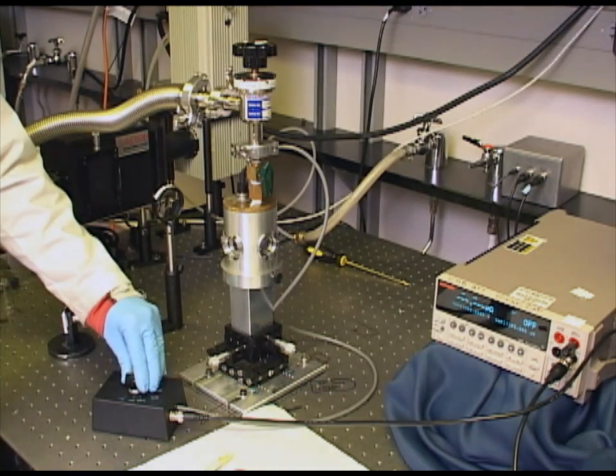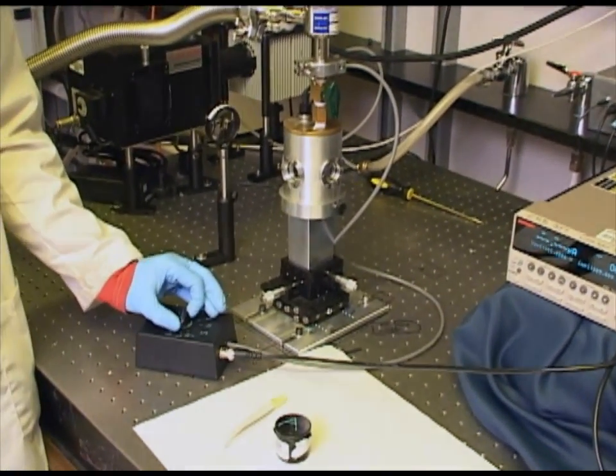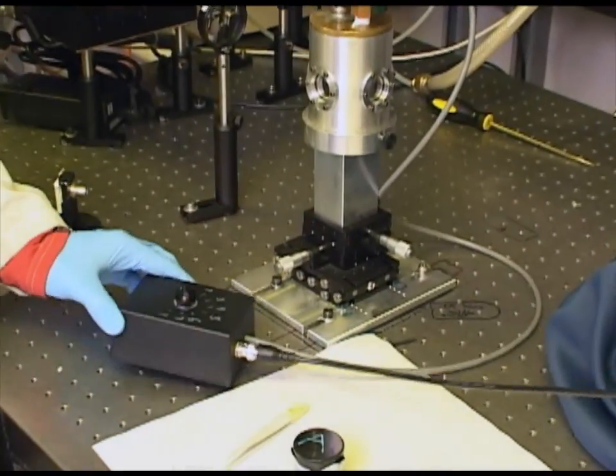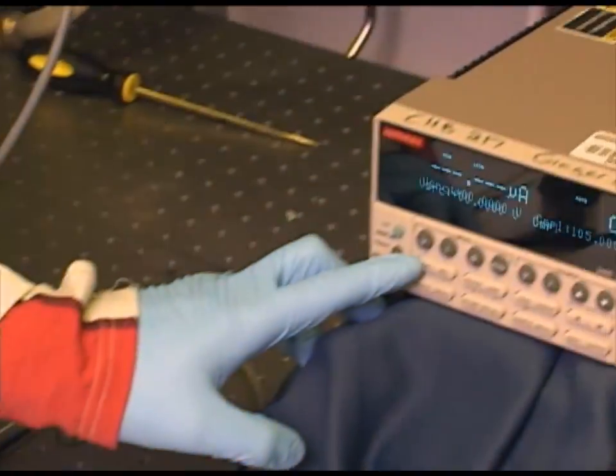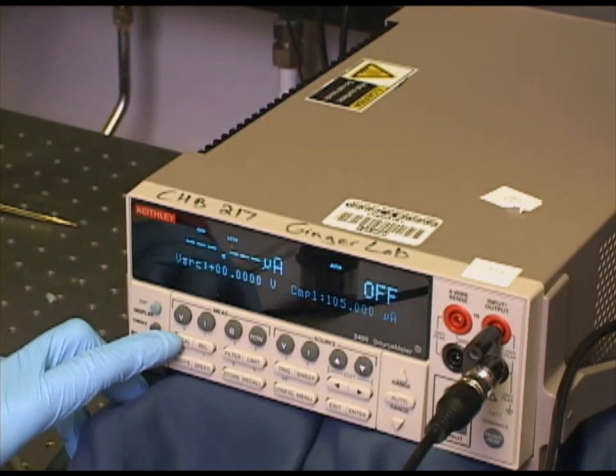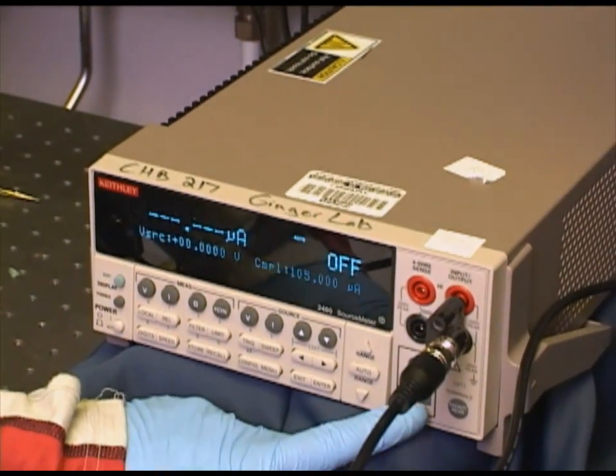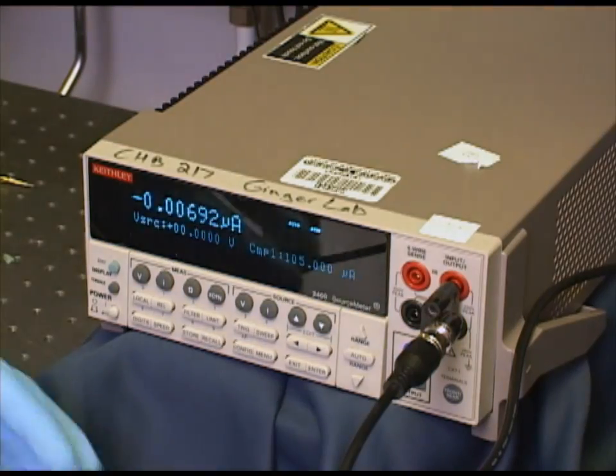I'll go ahead and attempt to align pixel 1. So I set the switch box to pixel 1. I turn the source probe unit on to local and output on. And then we get a live display of the current coming out of that device.